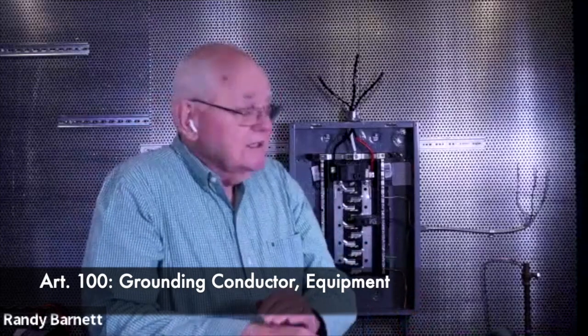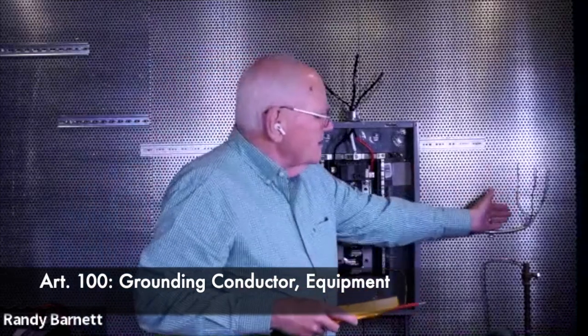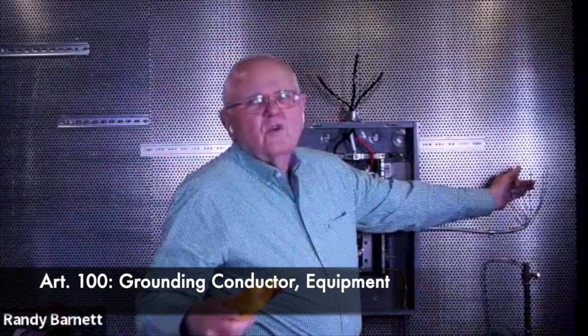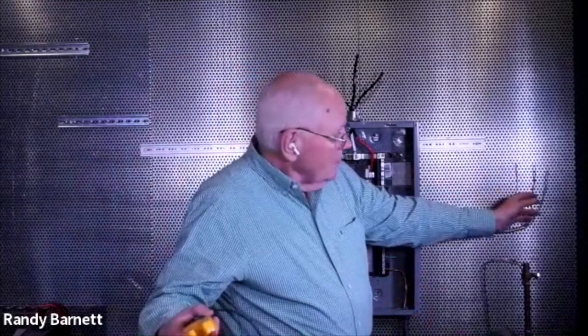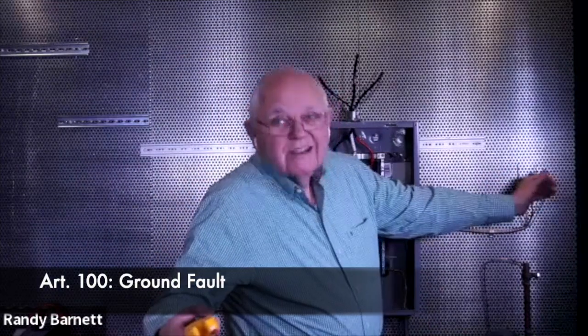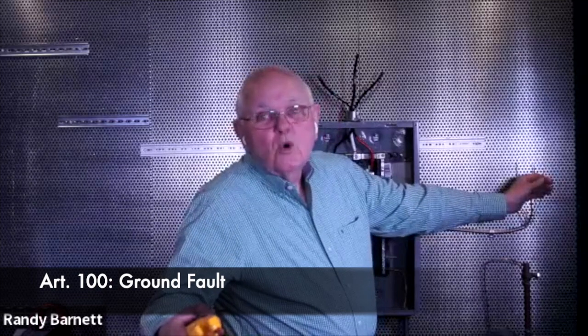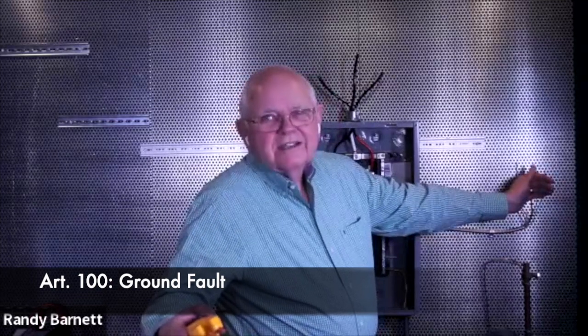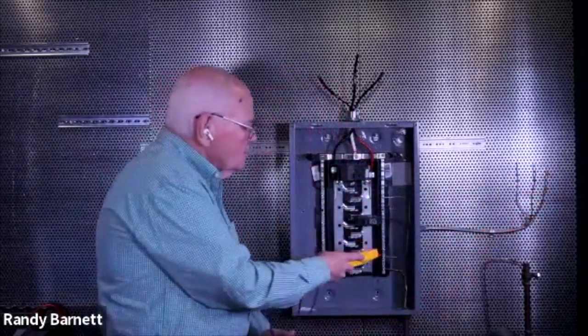What the equipment grounding conductor does is, if I have a fault out here, so normally current's going back and forth through the load in the black and the white wires, right? But if something flows into the frame, the metal frame of my equipment, unintentionally, and that metal frame does not commonly carry current flow, doesn't it? So we would call that a ground fault. So we're going to attach this green equipment grounding conductor. We're going to attach the equipment grounding conductor all the way back to the neutral bus bar.